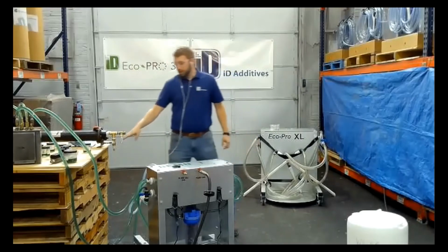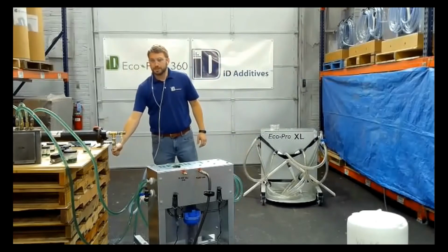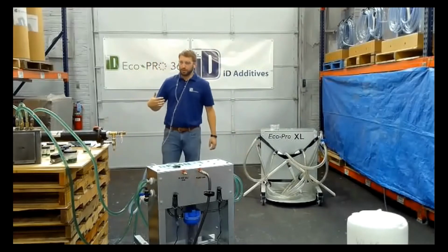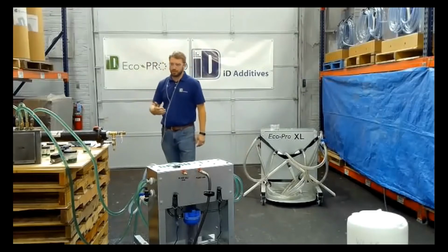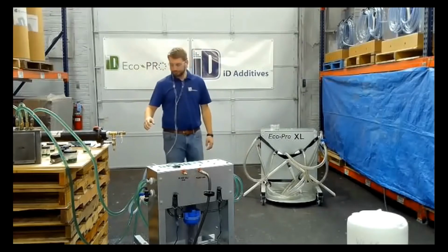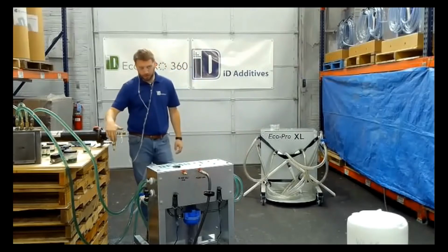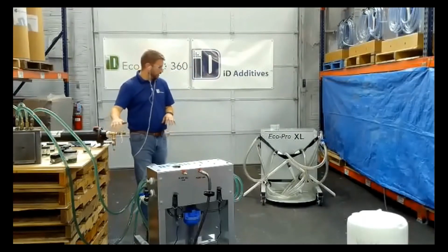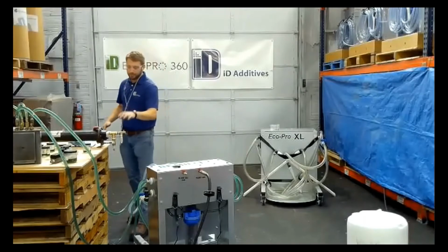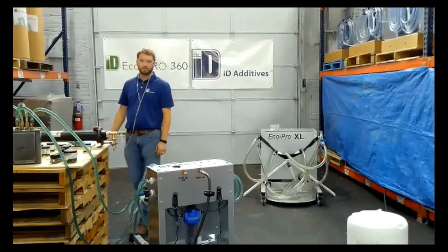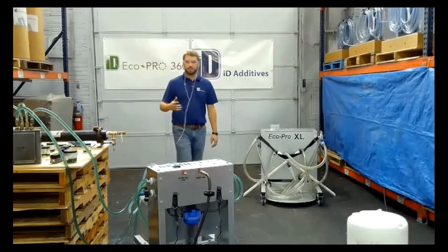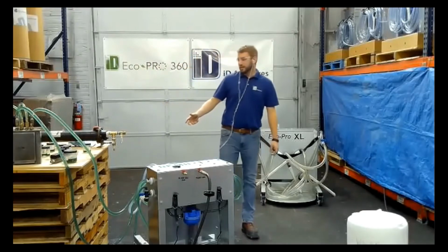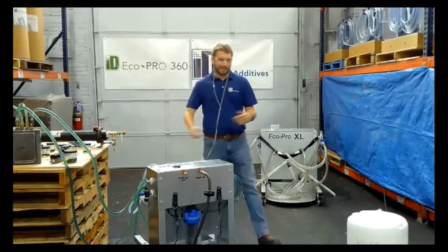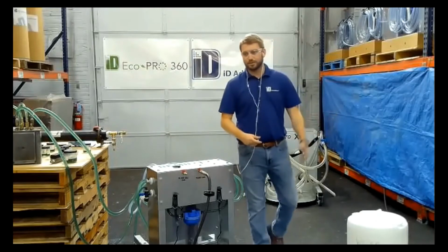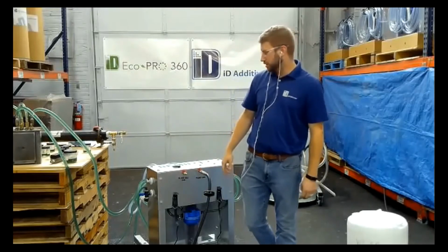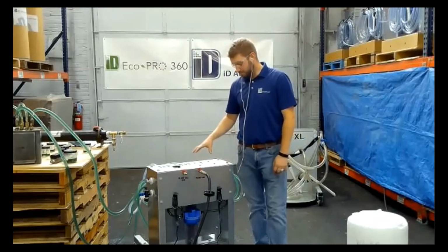All I did was plumb in quick fittings so those guys don't have to pull the heat exchanger off - you can just plug directly in. That's a nice way to do it. I was alluding earlier that whatever you have in your shop for flushing, have universal fittings. It's so important. There's been plenty of times when I go do a demo and hook up to one thing with a certain fitting, then I go to my toolbox and it's got a different fitting. So that's just one little tip and trick you can put in your shop.